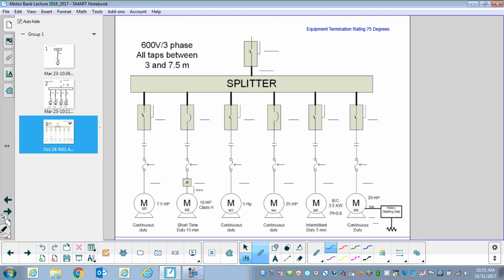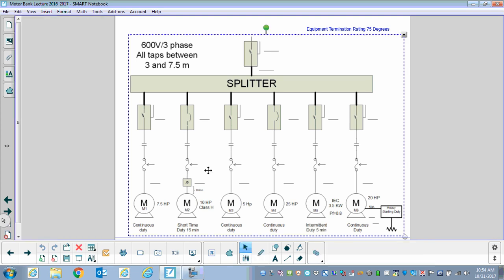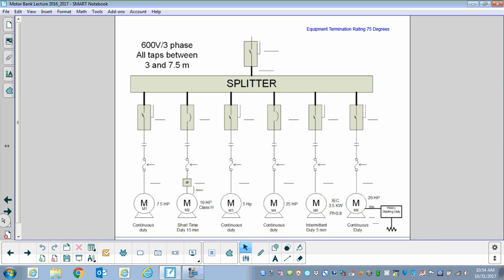We're going to carry on where we left off yesterday. We were looking at a couple of different motor configurations, and today I want to do the third worksheet. Here we have a 600-volt three-phase motor bank. All taps are between 3 and 7.5 meters. Our tap conductors are between 3 and 7.5 meters, and our equipment termination temperature rating is 75 degrees.